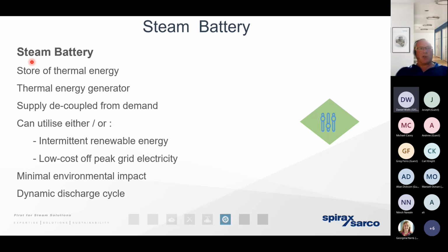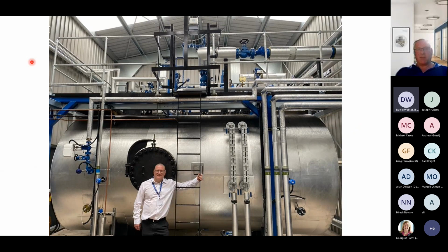In a typical thermal store, you can see a picture of myself there stood next to a thermal store that we've got in operation at the moment. This particular thermal store has a capacity of 14 cubic meters. Typically, we would fill it to around 80% full, so around 12 cubic meters of water. So that means we've got a steam space at the top of the store. If we charge that thermal store to 30 bar gauge, for example, and then drop the pressure downstream of the thermal store to somewhere around 1 bar gauge, we'd have approximately 1800 kilograms per hour of steam available, which equates to an energy of approximately 1 megawatt per hour for the process. So by moving towards a thermal store, this is a significant advantage for a significant number of steam using sites in helping them to move towards decarbonisation.